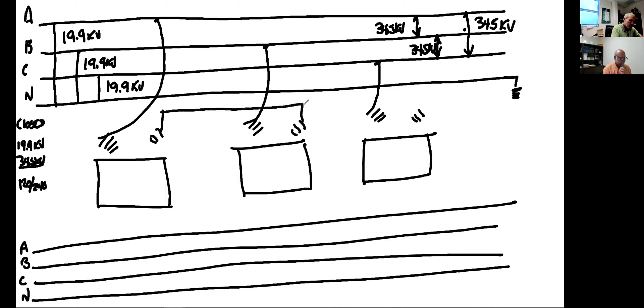All right, we've got 3 transformers, so we're going to be using all 3 phases. I'm going to make it easy on myself. A, B, C, left to right. Got my neutral bushing. Connected to that neutral bushing. Connected to that neutral bushing. Do I need to connect it to neutral that is grounded? No, no. This is the only bank that you do not do a connection at this point. I'm going to call that my floating neutral. Okay. Go ahead and draw my secondary bushings here.